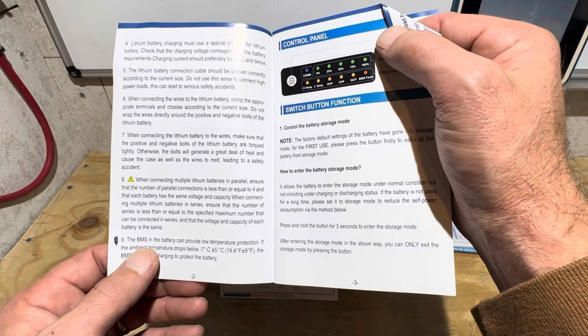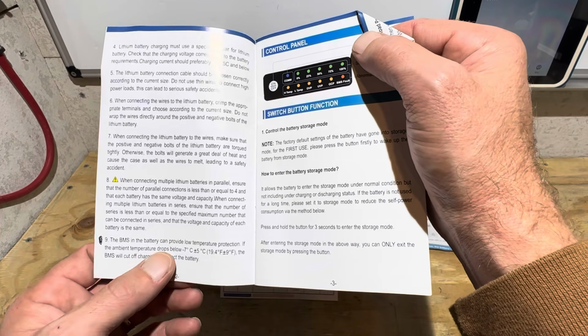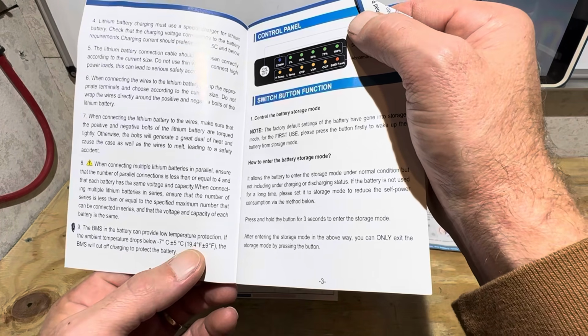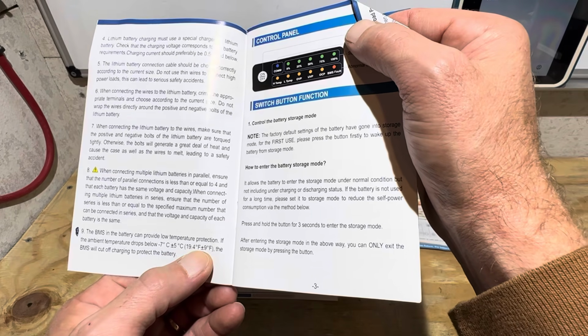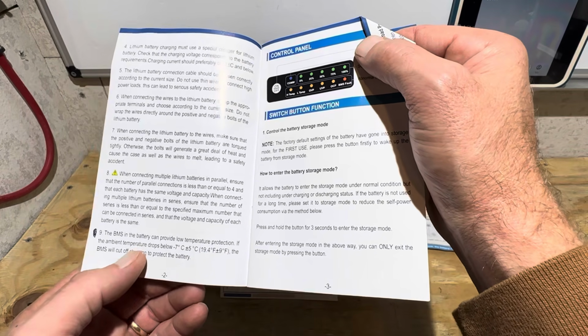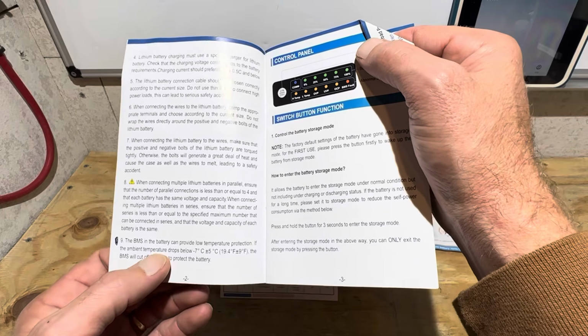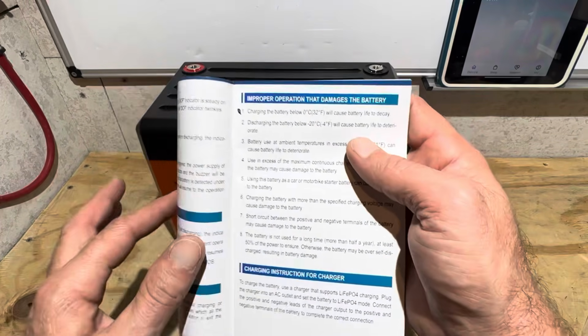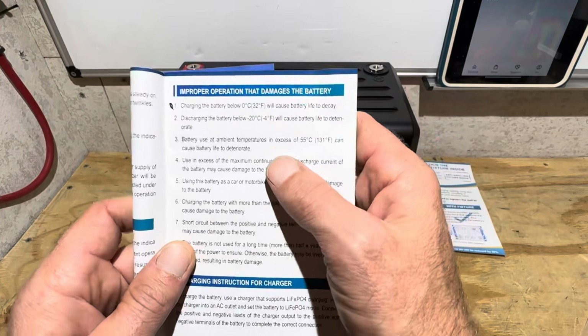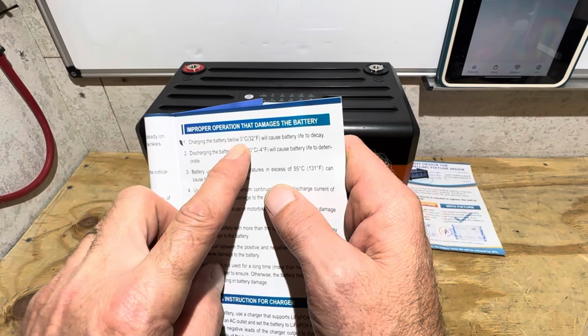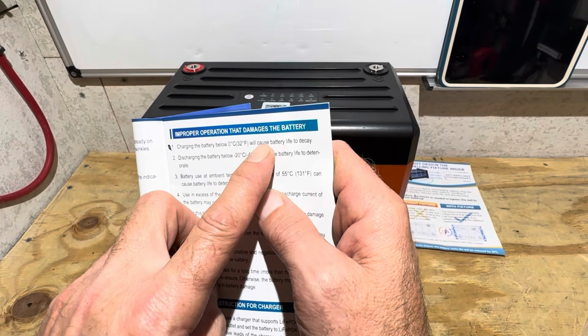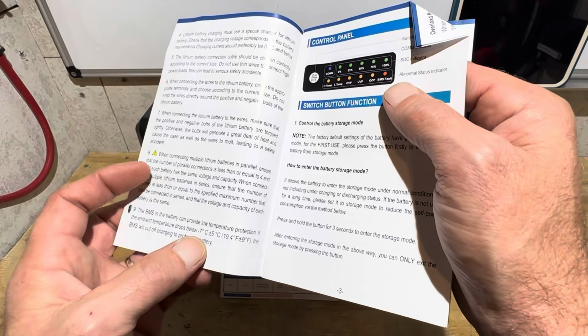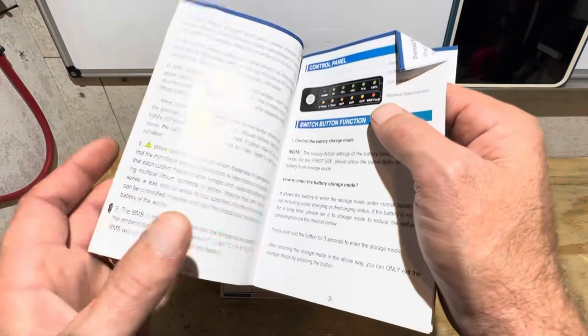The BMS in the battery can provide low temp protection if the ambient temperature drops below 19.4 Fahrenheit plus or minus 9 degrees Fahrenheit. All right, so that's, I'm assuming, their low temperature charge protection point. And look right here, improper operation that damages the battery: charging the battery below 32 degrees Fahrenheit will cause battery life to decay. Well, if that's the case, why did you program your low temp protection point so low?